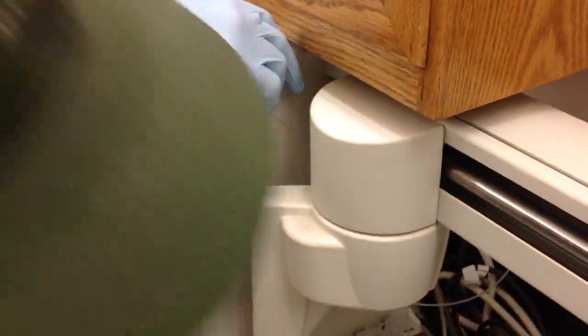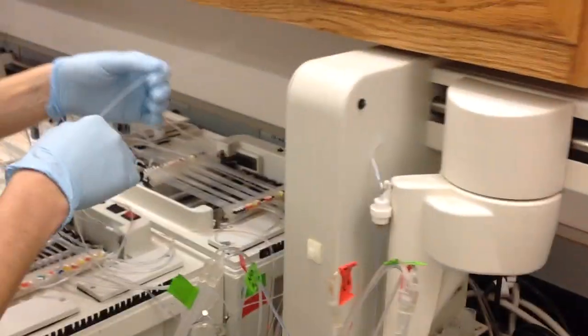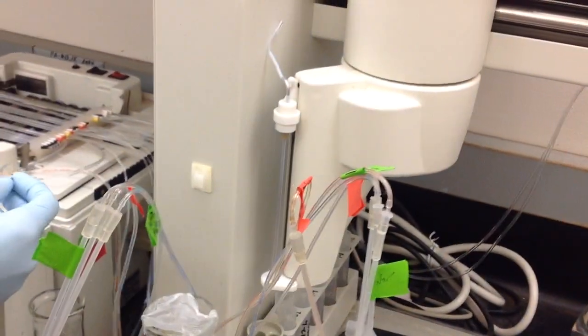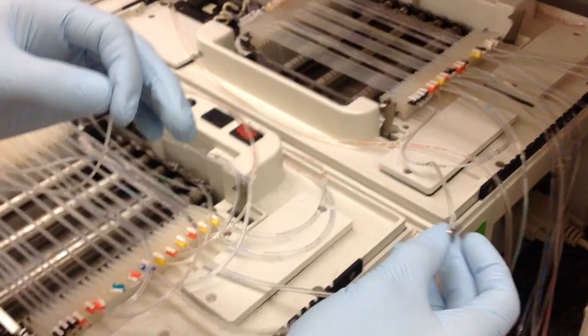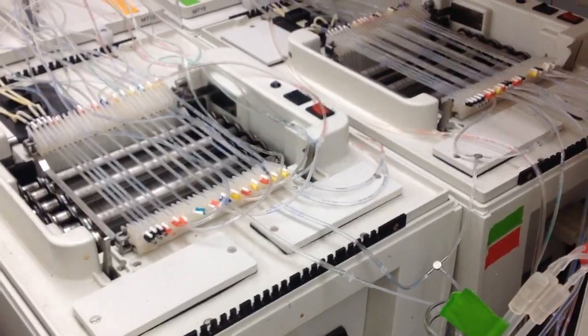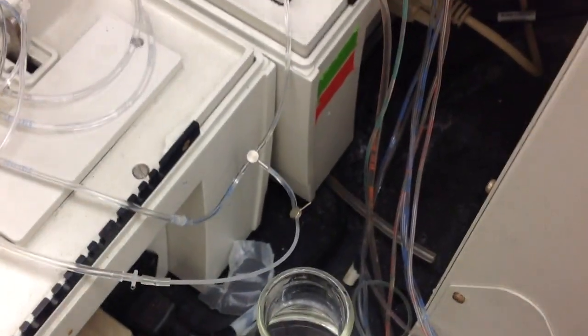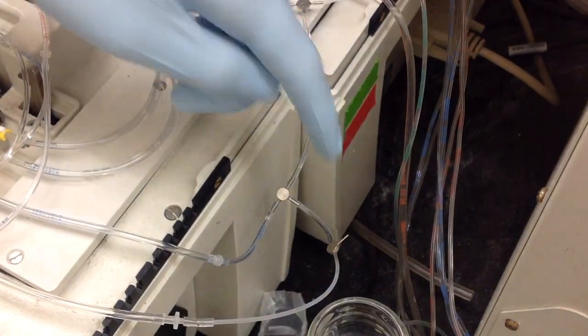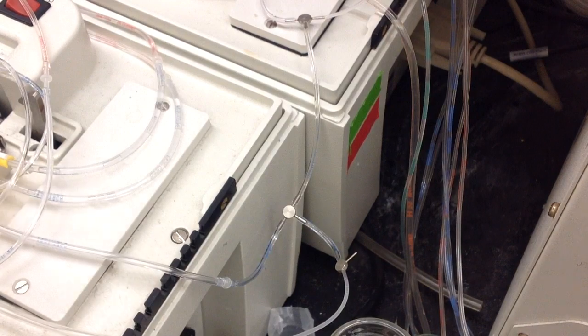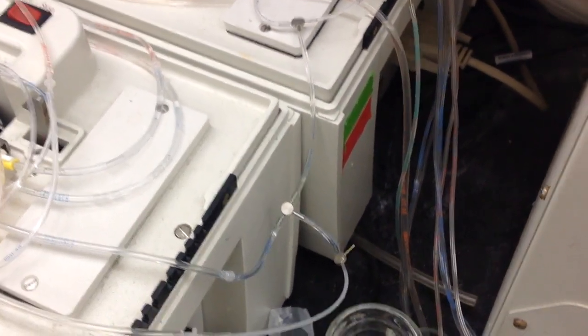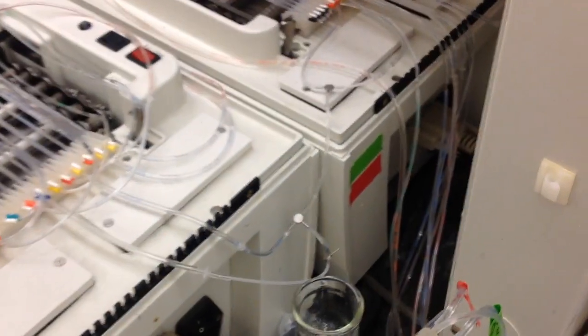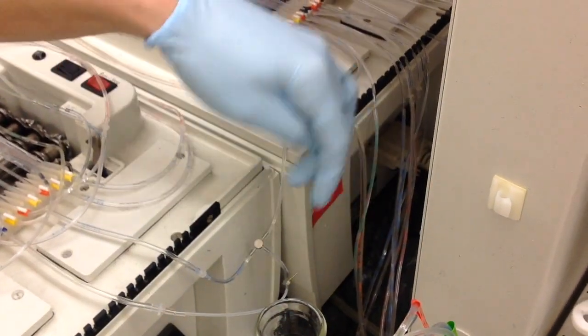So this is a pretty long line, one of the longest lines you're going to have to cut. Any of the metal junctions, you shouldn't have to replace, unless they get really, really clogged. Or I should say, unless you're running some really dirty samples, these shouldn't need to be replaced. They should be able to be cleaned through regular flushes of bleach and acid and soap, or sodium hydroxide, basically the soap.